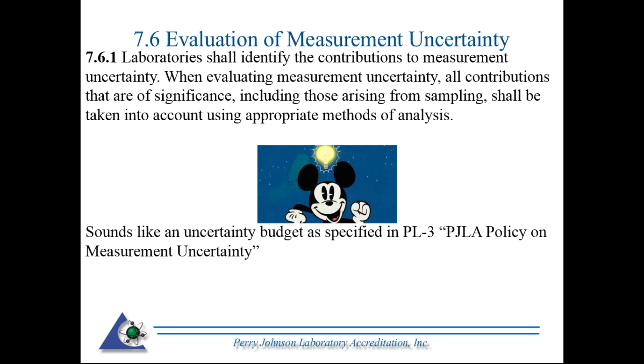Diving right into the requirements under 7.6. 7.6.1, laboratories shall identify the contributors to measurement uncertainty. When evaluating measurement uncertainty, all contributors that are of significance, including those arising from sampling, shall be taken into account using appropriate methods of analysis. When I read that, I think, well, heck, that sounds just like an uncertainty budget. Those folks that are logged on from calibration, I know you're familiar with uncertainty budgets, as we have specific requirements in them stated in PL3, which is PJLA's policy on measurement uncertainty.